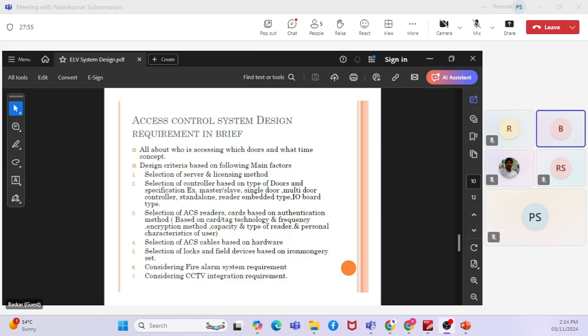So in the master slave concept, the master is holding the complete memory, and the slave controllers are connected through RS485. I believe you are aware of the RS485 method. That's a two-wire system. Mostly the master controller will be an IP-based controller, and the slave controllers will be on the two-wire RS485 system. So we can have a master slave concept, or if the client requires only IP-based controllers, then we cannot go with the master slave controller.